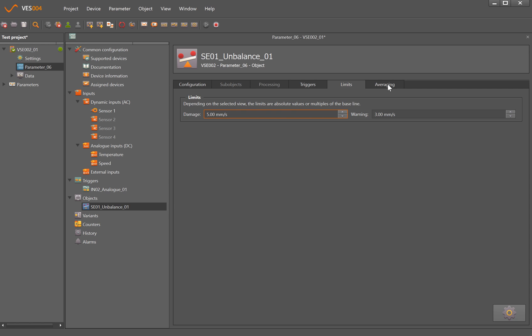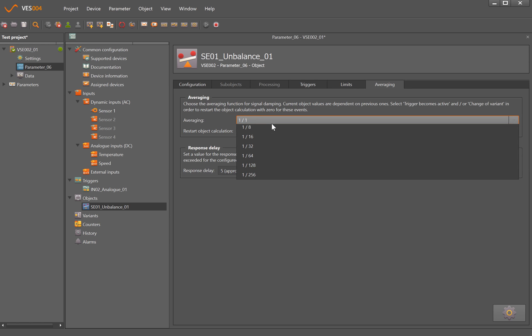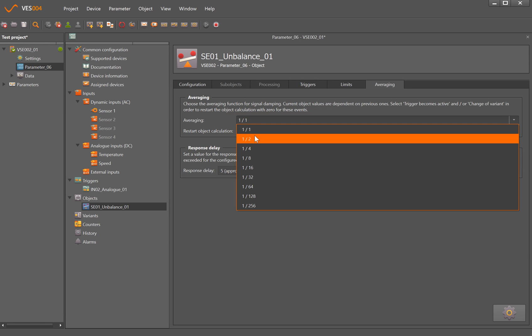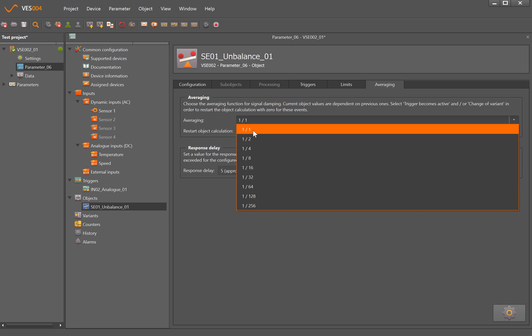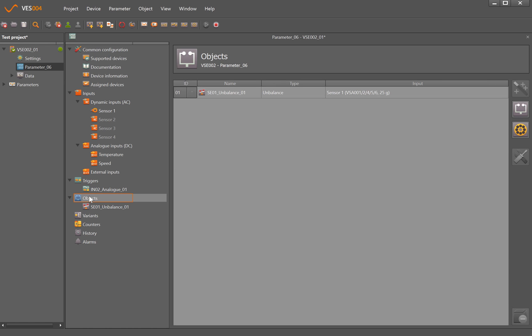And we also have averaging as well where we can sort of damp down the signal, so rather than working on every calculation and referring to that number, we can maybe take every four calculations and then the number that's the average of those four is the value that the software would calculate from. We can also put in response delays here as well, so that if something does go into alarm it holds that off for a period of time until it physically alarms, just to stop any spurious signaling.